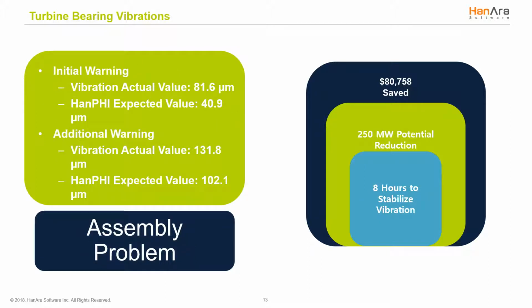The second case occurred in February 2017 when HanPHI helped an 800 megawatt thermal power plant save approximately $80,750 in maintenance and operation costs by providing early warnings of increased turbine bearing vibrations. After an overhaul, HanPHI identified a vibration issue on one of the turbine bearings. The vibration was 81.6, while HanPHI's model expected 40.9 based on the current plant condition.